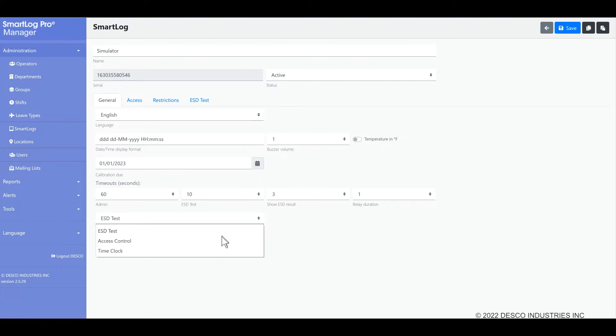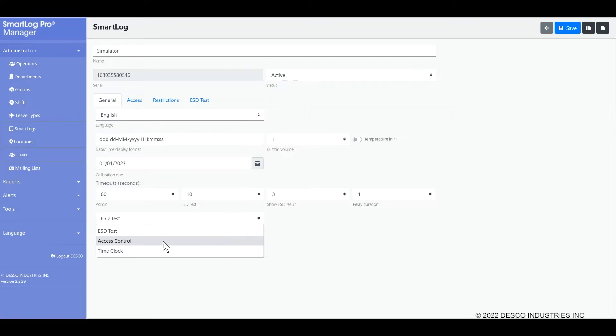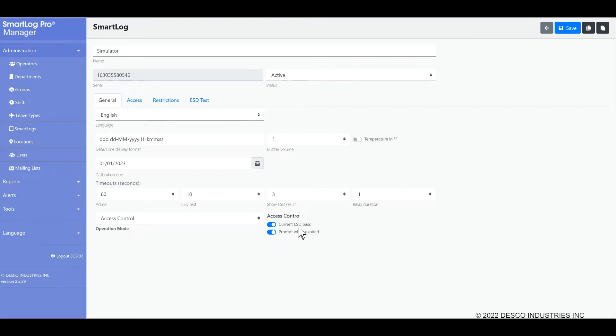Access control is a specialized mode that is used when you want to strictly enforce testing and restrict operators from accessing certain areas that are being controlled by multiple SmartLog Pro SE units via their relay connection to a door or turnstile, for example. When you select access control, some new fields become available. Current ESD pass is one of them. When enabled, operators are required to have a previous ESD status of pass in order for the relay to trigger and be granted access.